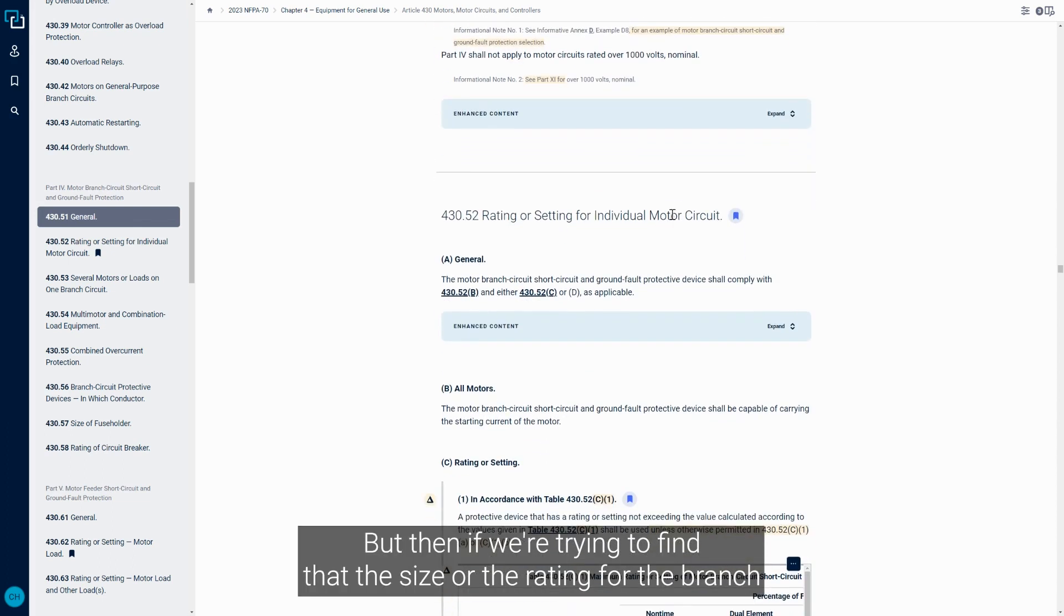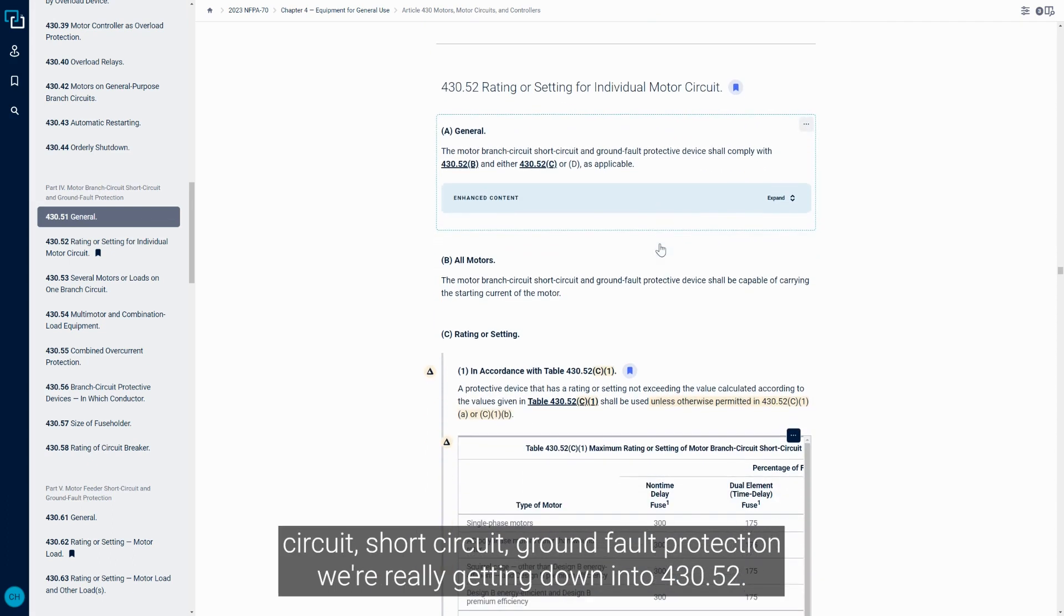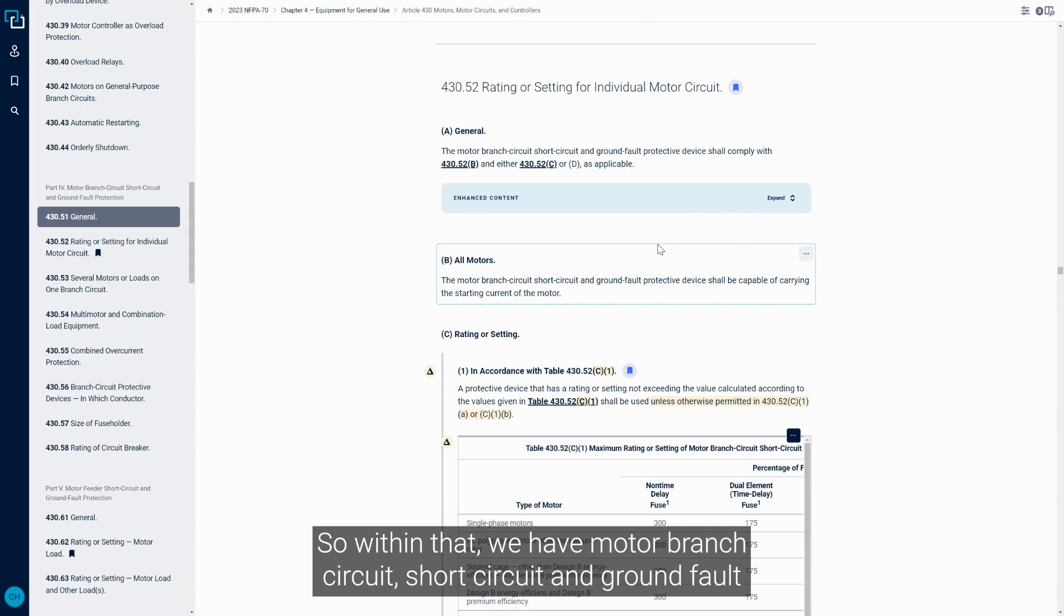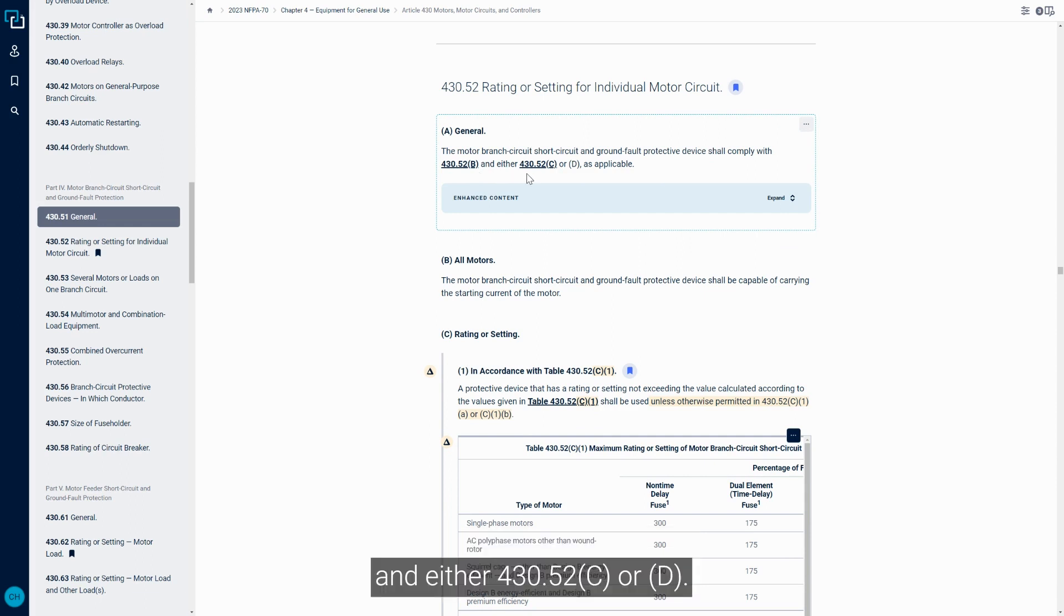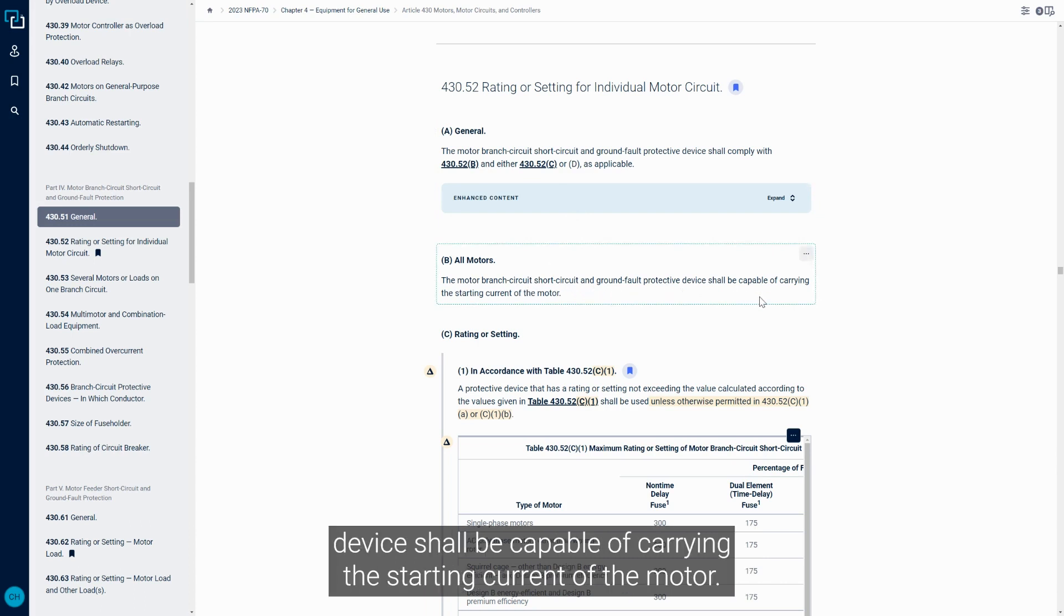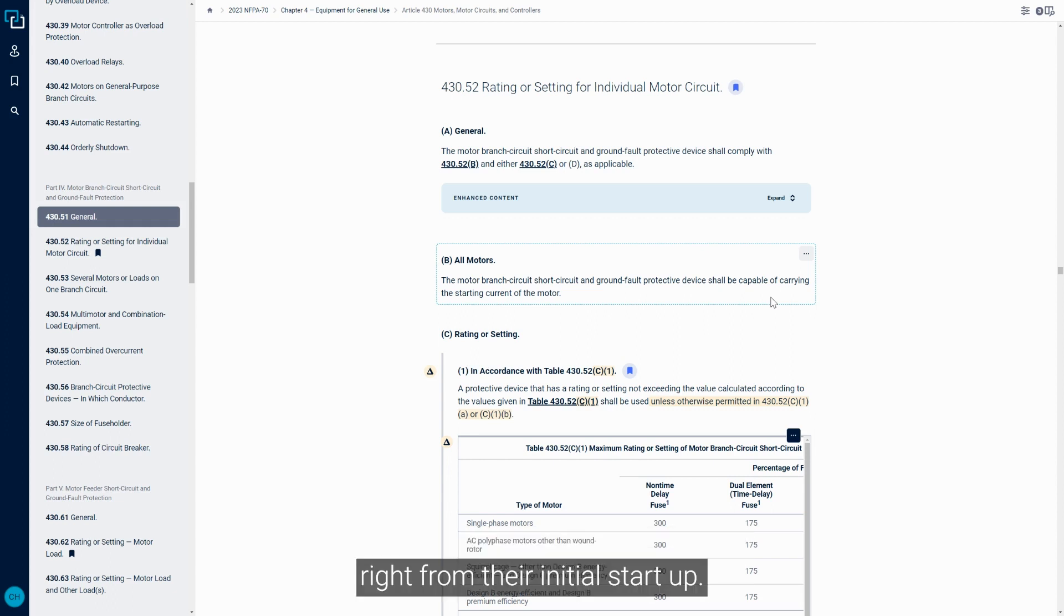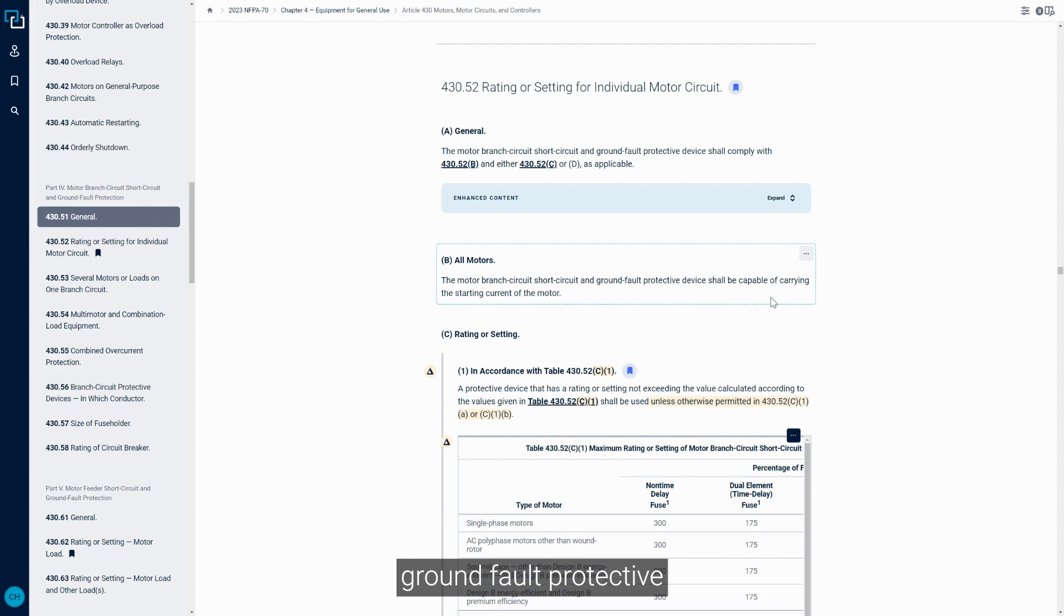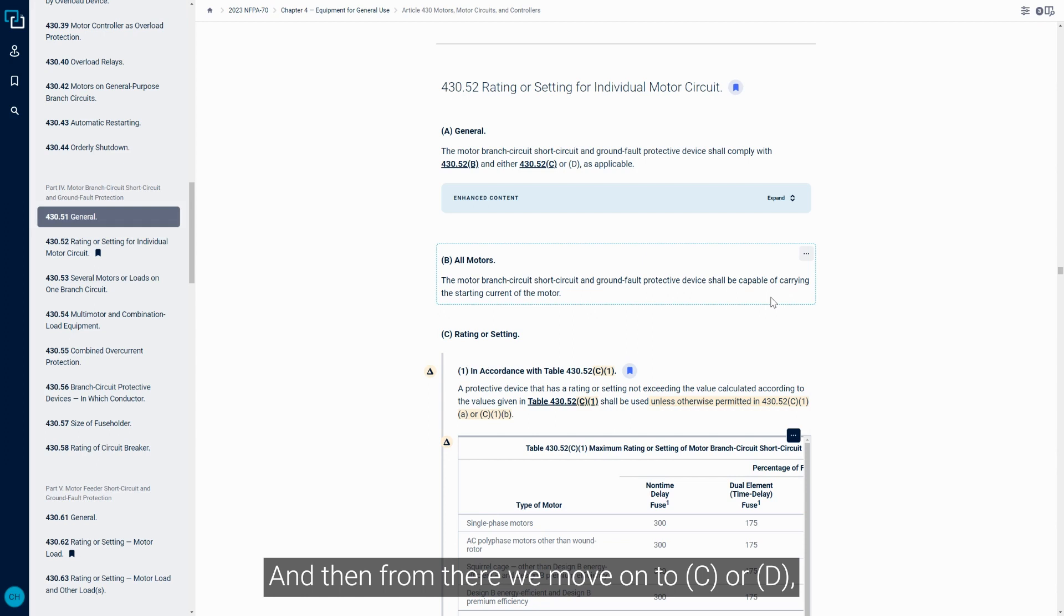If we're trying to find the size or rating for the branch circuit short circuit ground fault protection, we're getting into 430.52. Motor branch circuit short circuit and ground fault protective devices must comply with 430.52B and either 430.52C or D. Section B states the protective device shall be capable of carrying the starting current of the motor. With motors, there's typically an inrush of current from initial startup, so these fuses have to withstand the starting current.